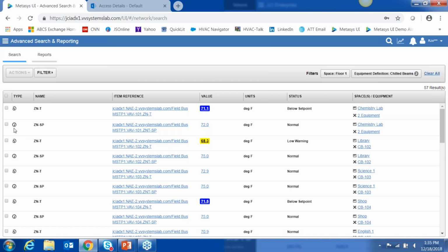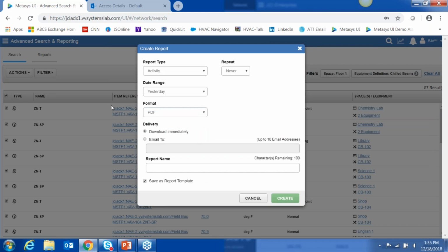What I want to show you that we released at release 10 is if I select some writable points and some non-writable points, all the zone temperatures and all the zone set points, and go up to the action button and go to create report. I can generate a report that shows either activity, which is a combination of alarm and audit activity, or I can select just an alarm report or an audit report, which are user transactions, or historical trended data. Those are the four types of reports I can select and create here.